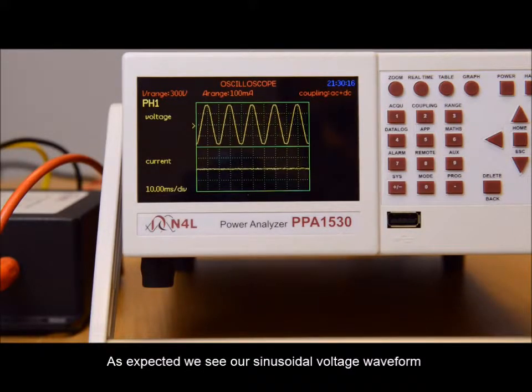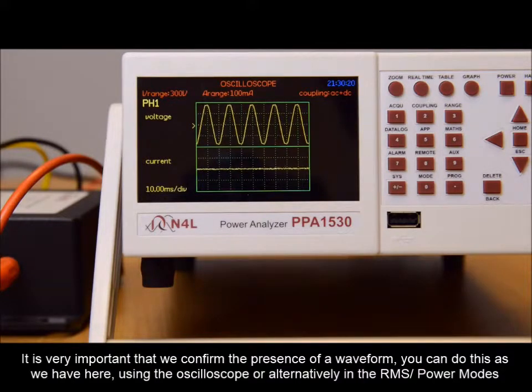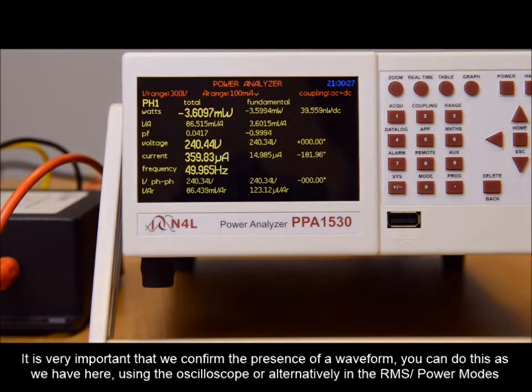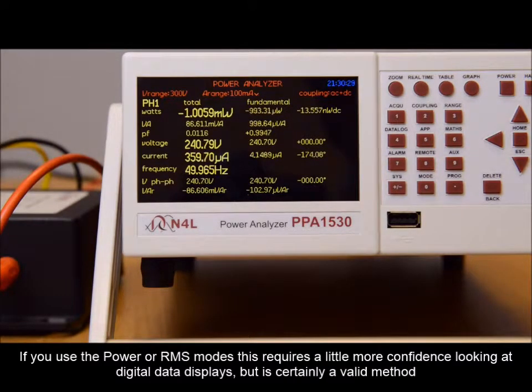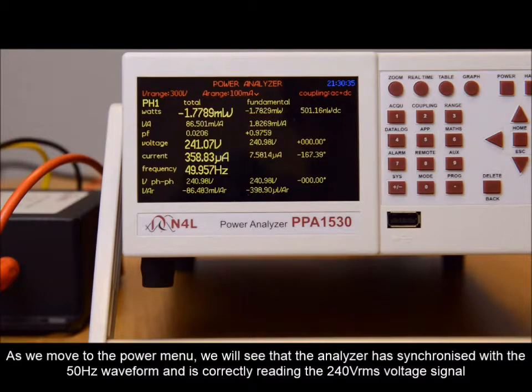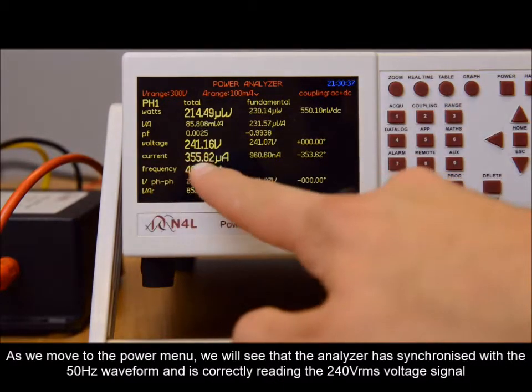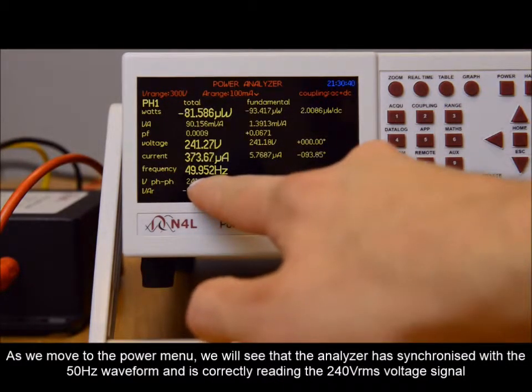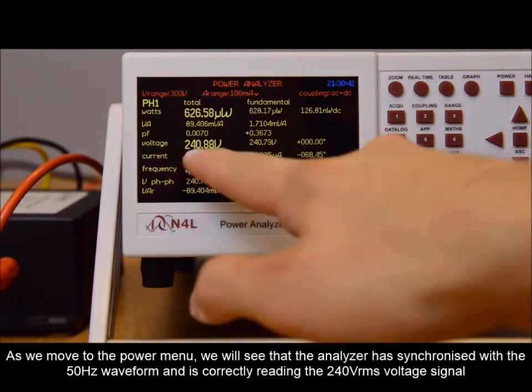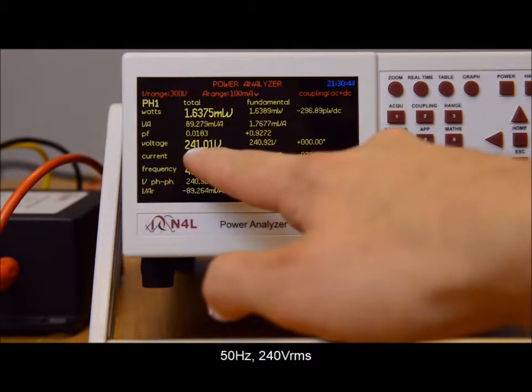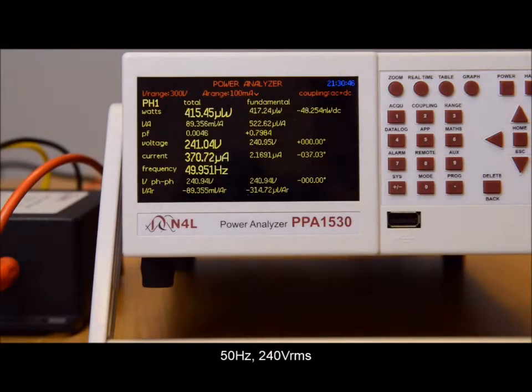As expected, we see our sinusoidal voltage waveform. It is very important that we confirm the presence of a waveform. You can do this as we have here using the oscilloscope or alternatively in the RMS or power mode. If you use the power or RMS modes, this requires a little more confidence looking at digital data displays, but it's certainly a valid method. As we move to the power menu, you will see that the analyzer has synchronized with the 50 Hz waveform and is correctly reading the 240 volt RMS voltage signal. 50 Hz, 240 volt RMS.